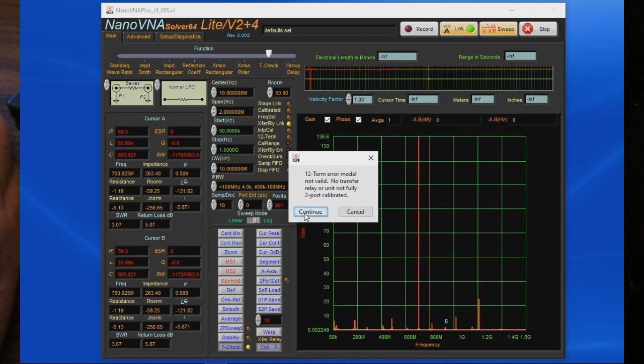The software says that the 12-term error model is not valid. There's no transfer relay, or the unit hasn't fully been 2-port calibrated. We're going to go ahead and select continue. And you can see this is not very good at all. Again, if we're looking at the vertical axis, this is in percentage. According to Rohde & Schwarz, anything below 10% is very good, between 10 and 15% is fair, and anything greater than 15% is a poor calibration. So even at 50 kilohertz, this calibration isn't any good.